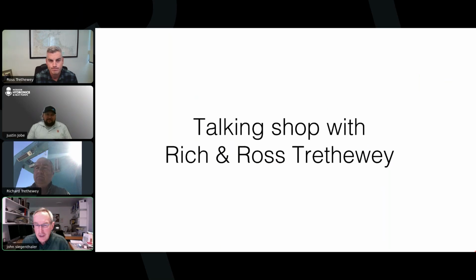Justin, I think you were telling me about a pretty unique solution involving Vaseline. You want to jump in on that? Well, I do a lot of hydronics training, and I will say in today's world, chilled water cooling is definitely getting easier. I'm motivated to do what we can on our side to further that development. Things like insulated volute pumps, but having a few install techniques to help goes a long, long way. It's not the valve that actually rusts and looks terrible. It's the plated handle and the nut on the ball valve. And in most cases, with ball valves, you're not opening and closing them constantly.